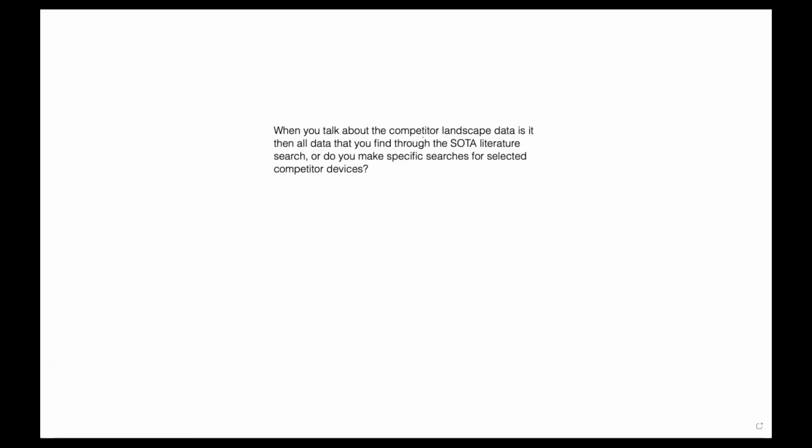To support the state-of-the-art section, that to us is two searches. One is more of a PICO search for state-of-the-art literature, where we're looking at patient and indication, and we're looking for guidelines and references and background information. Think of it that way. That search doesn't need to be screened. The MDR doesn't require that you screen that search, but looking for background information to tell the story is the easiest way to say that.